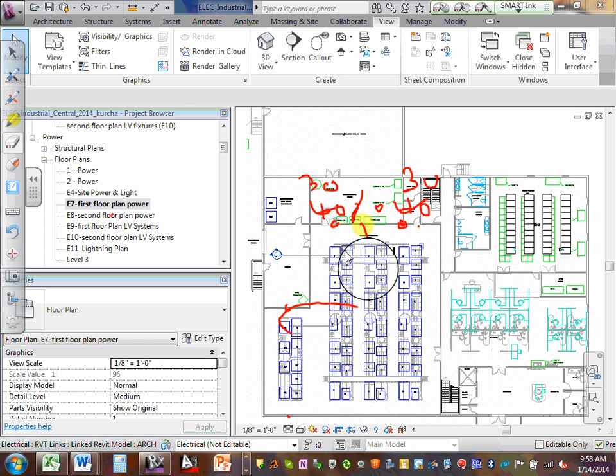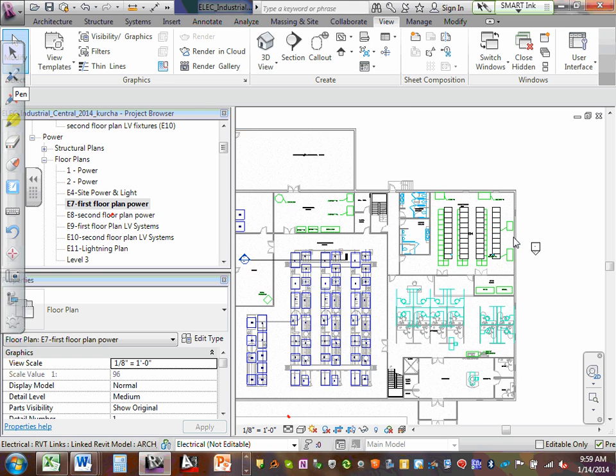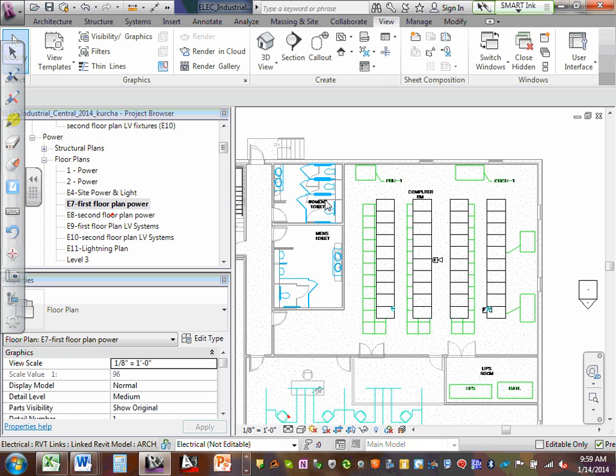Let's go to the data center. There's a pre-action sprinkler system being provided in the data center, and there's also a raised floor in the data center. The raised floor is usually installed in the data center so that all the cabling for all your computer equipment runs under the floor. It's a great place for fires to start. There's an awful lot of electrical equipment under there, high voltage, low voltage, you name it, data cabling, it's all there.